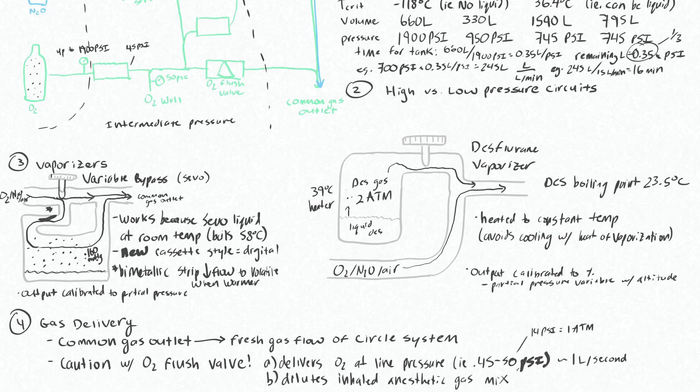The second issue with this is that it dilutes your inhaled anesthetic gas mixture. You spent all of this time precisely titrating your gases through the flow meters to get a certain percentage of oxygen, air, and nitrous, and then getting a certain percentage of volatile from your vaporizer and sending that to your common gas outlet. But when you flush through this O2 flush valve, you're just delivering 100% oxygen. You will no longer be sending a concentration of gas that is an anesthetic to the patient, and that is counterproductive.